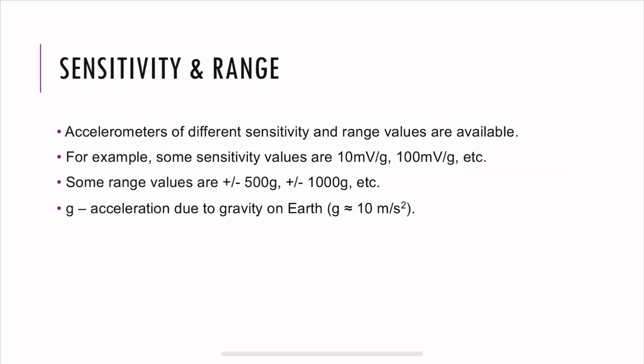There are also sensitivities and ranges of the accelerometers. They have different values. For example, some sensitivities are like 10 millivolts per G, 100 millivolts per G, and ranges are like plus minus 500, 1000. Usually you see in Gs, but you can also have a different unit, which is millivolts per meter per second squared because G is nothing but the acceleration due to gravity and we're approximating it as 10.